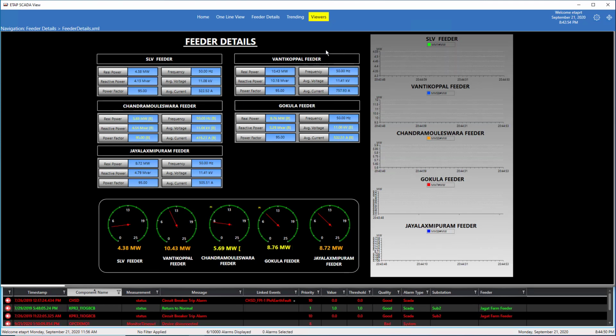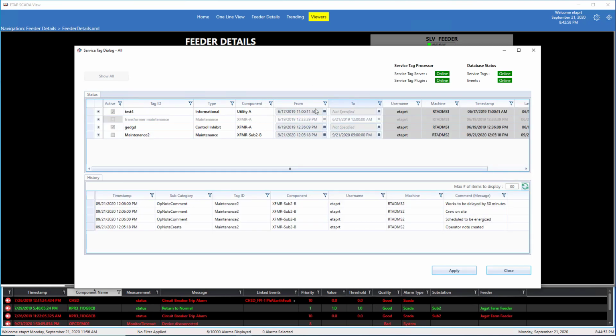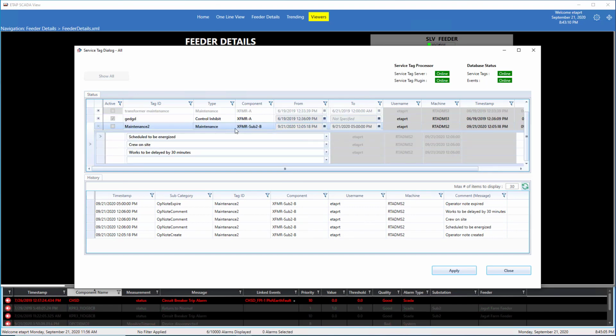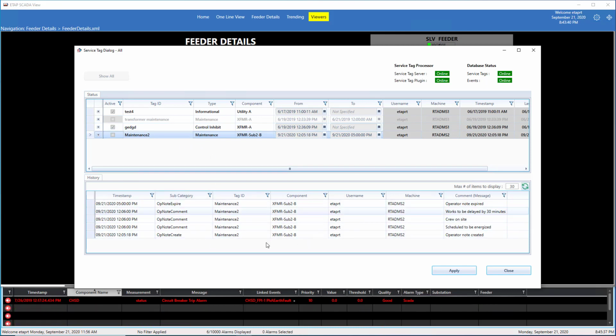Another important tool to have at the substation is your service tags view. The service tag view gives you any tag-out information that has been created on the system. For example, here I can see that there is a maintenance tag on transformer B in substation 2, and I can see the notes that are being created either by the crews or by the operator of the substation. We can see that at a certain time this was scheduled to be de-energized. The crew came on site, works got delayed, and so on. All this information is kept in the historian, so you can go back and see what happened.